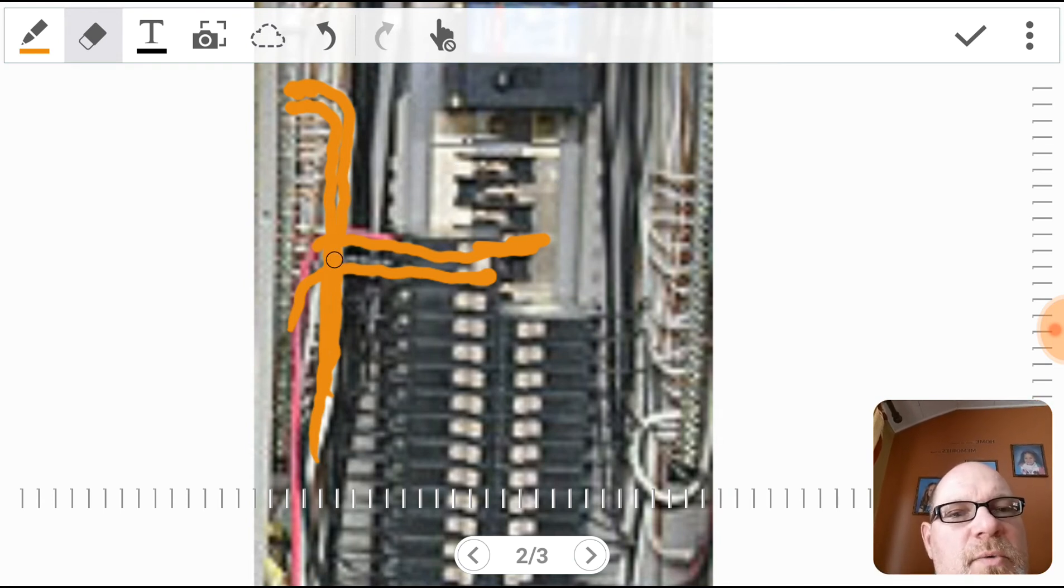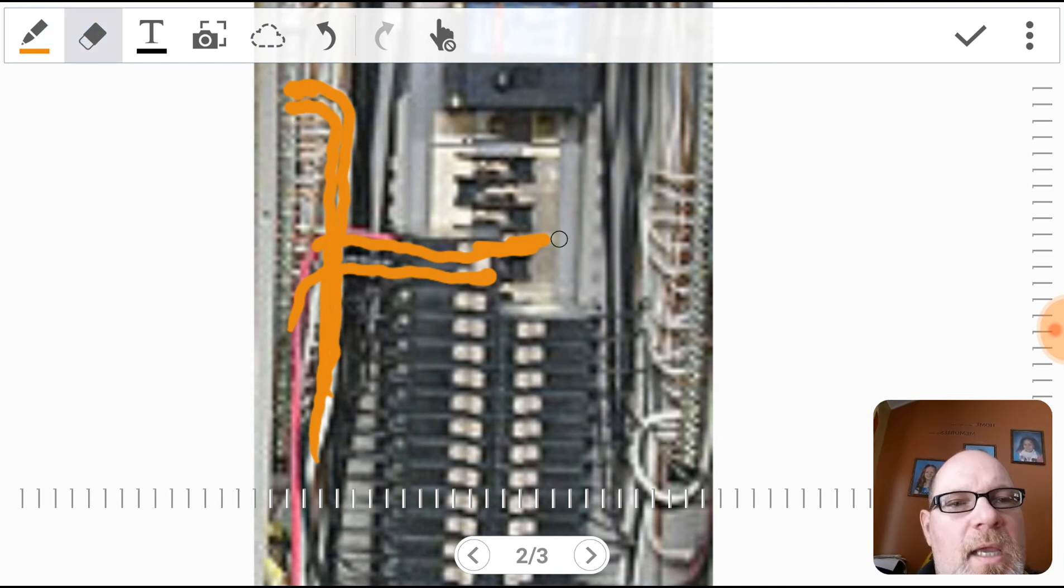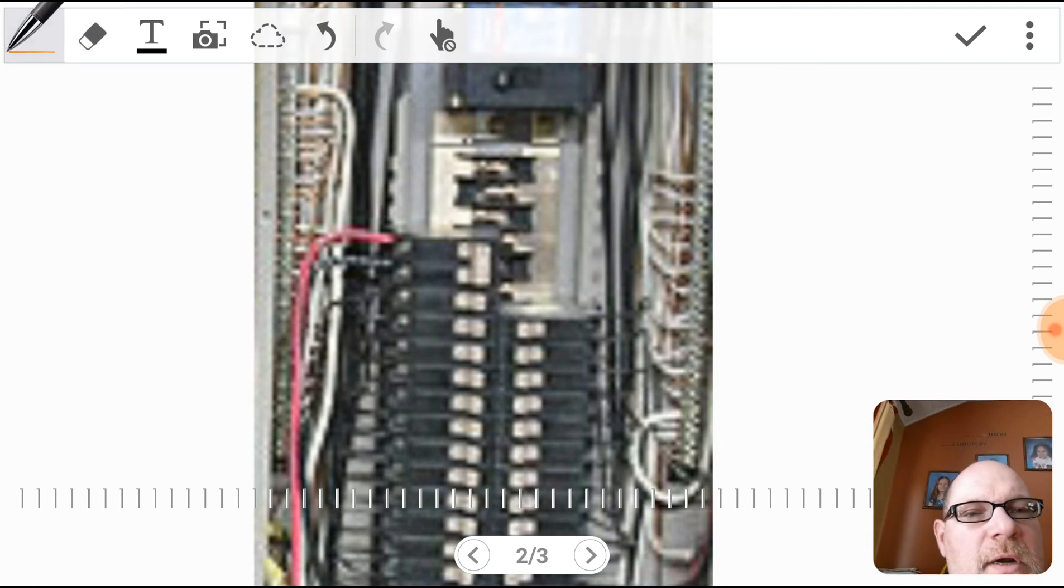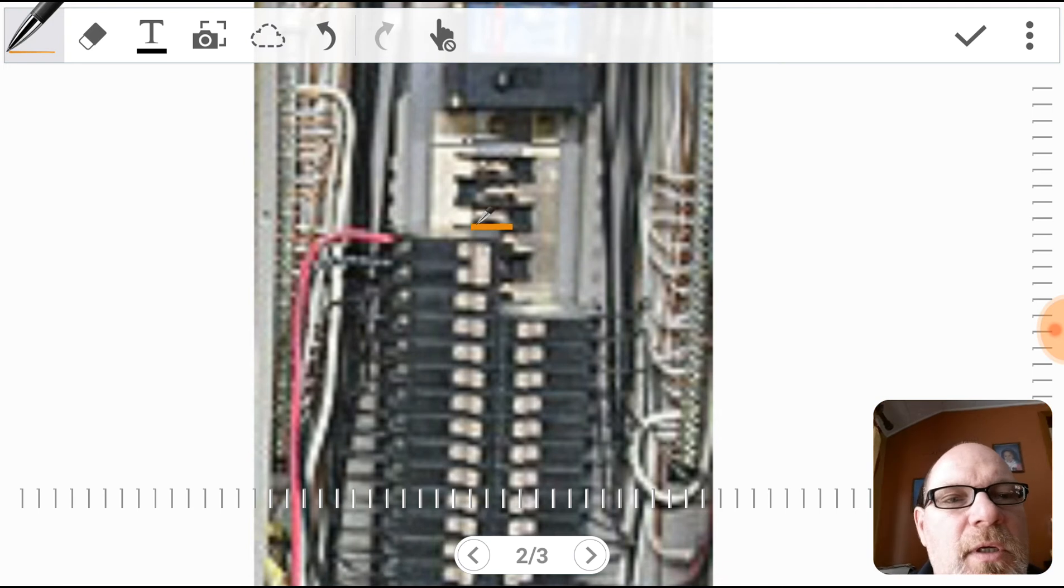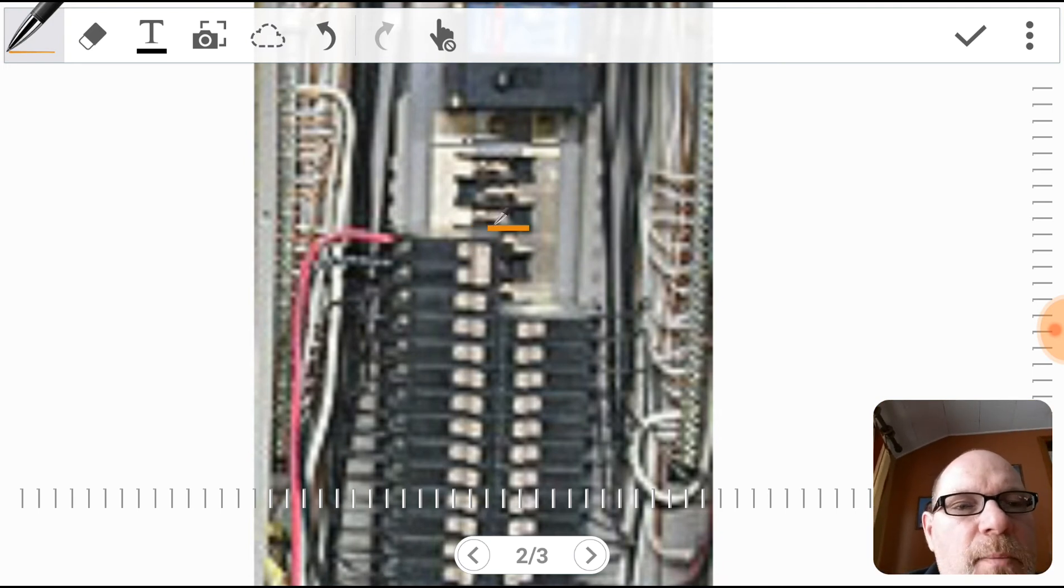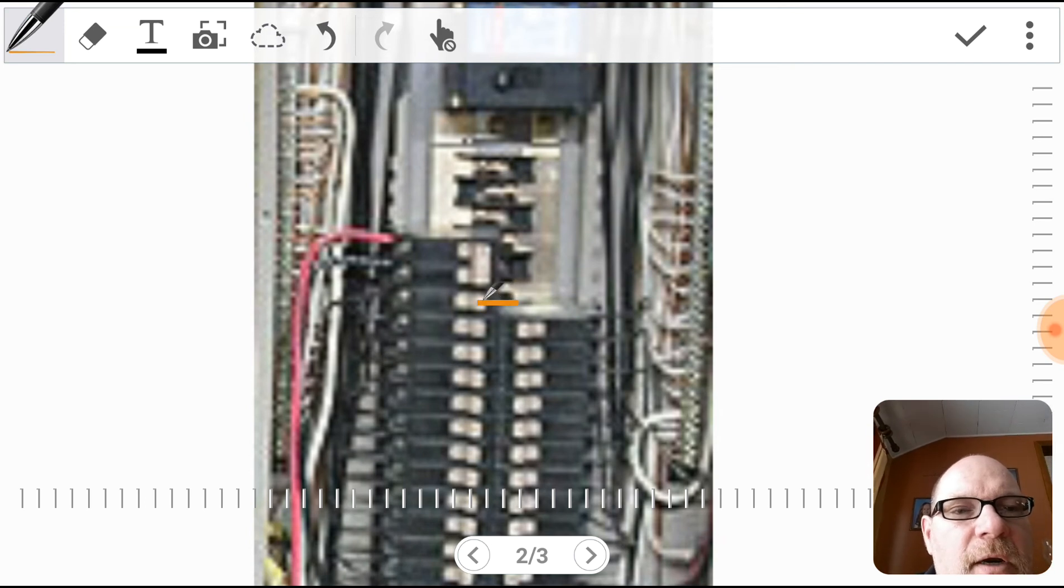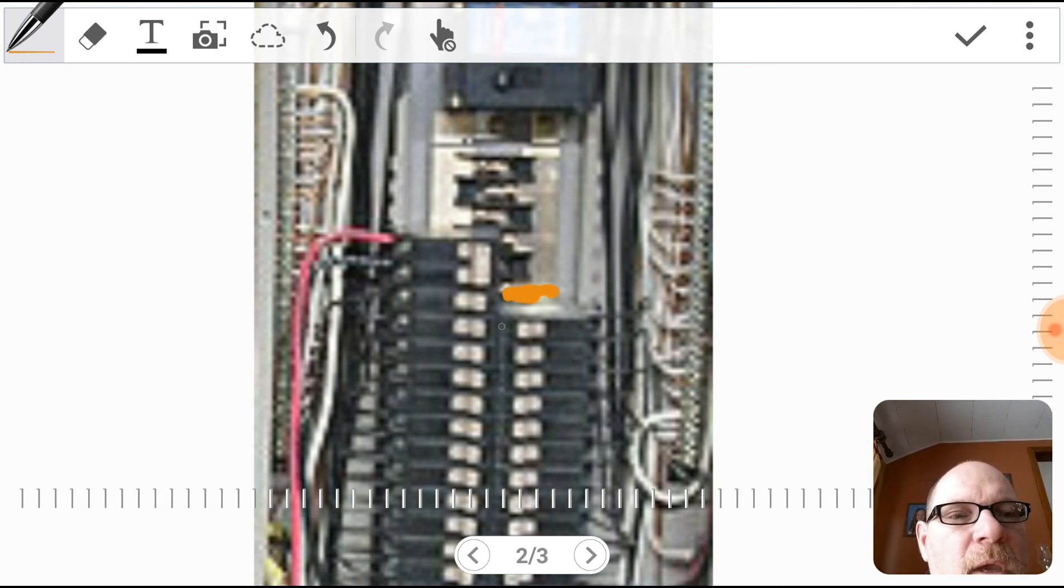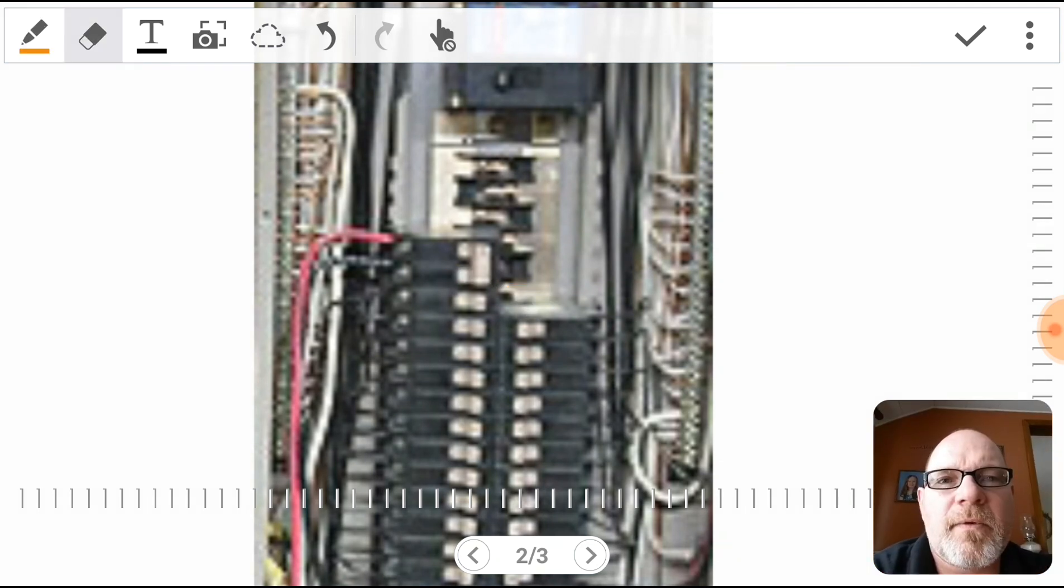Okay, now this bus and this bus again, L1 and L2, that's how 220 breakers are wired up. A 120 breaker is wired up similar, however a 240 volt breaker is a two-pole breaker and a 110 volt, say a 15 or 20 amp breaker, is a single pole. So a single pole is going to connect to just one side - it might be L1 or it might be L2, just depending on the location of that breaker.